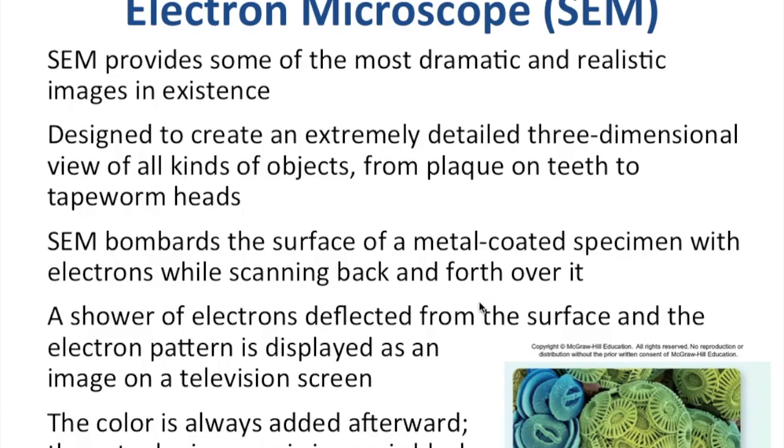That's why the scanning electron microscope can be used to visualize the surface of the samples. Since it requires the reflection of the electrons, we have to prepare the samples with a specific method, such as coating the surface of the samples with metal. Normally we use a very expensive metal, such as gold, to coat the samples.